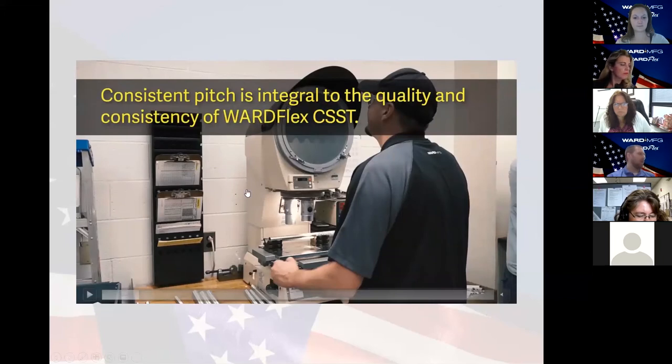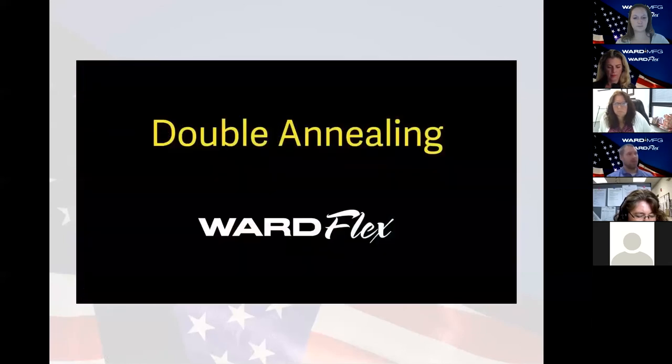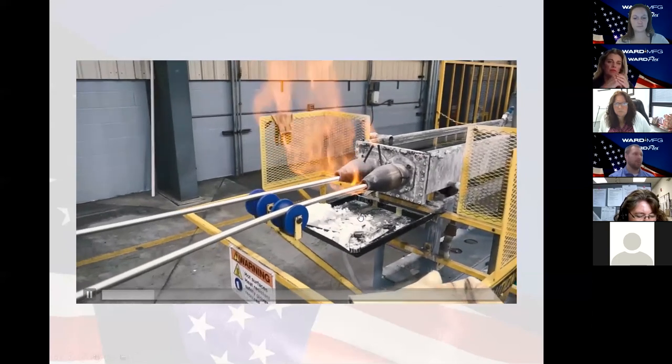And then you'll see here that after the tubing is made, a piece from each drum that's made goes in the lab, and a quality technician actually does measurements on a comparator here. And there they check the pitch, the diameters, and all the critical dimensions.